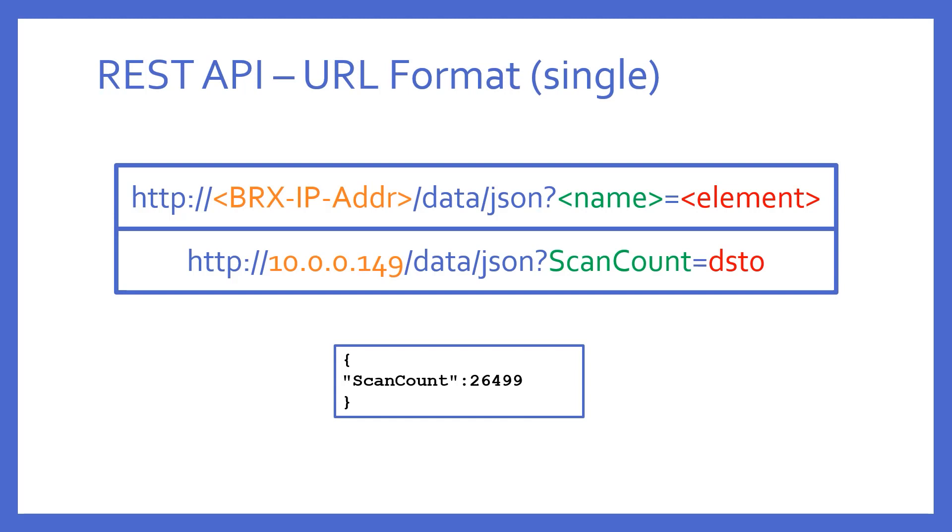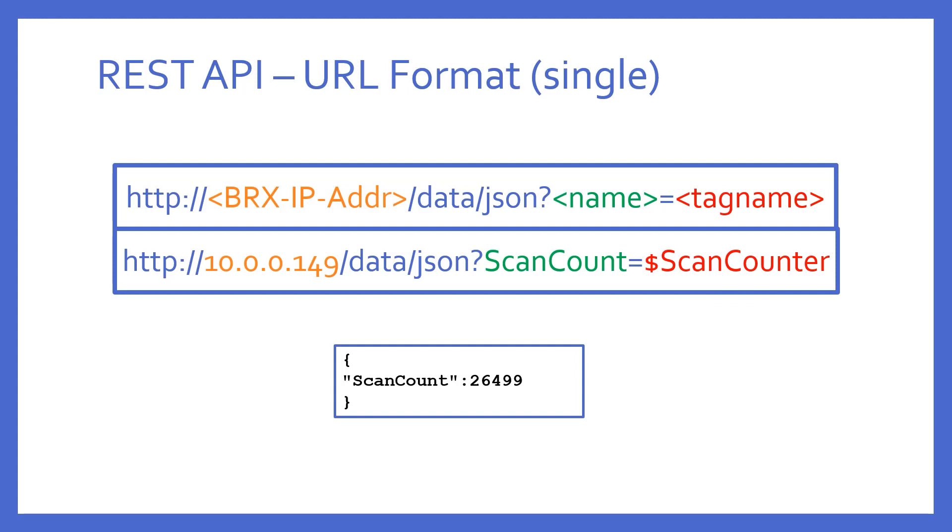Another very important thing to know is that I don't have to use the raw element name like DST0. Instead, I could use the tag name. This is also called a nickname in Do More Designer that is either automatically assigned in the case of system elements or one that you have previously assigned in your BRX PLC. This would change the example to use $scancounter, which is the tag name of the system element DST0. The result would be exactly the same. You need to keep this in mind because most people, when programming a PLC, utilize tag names extensively since it makes more sense to have a familiar name for the elements rather than the raw, less relevant element name.